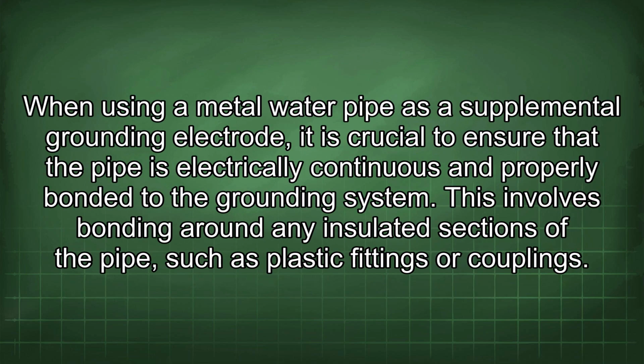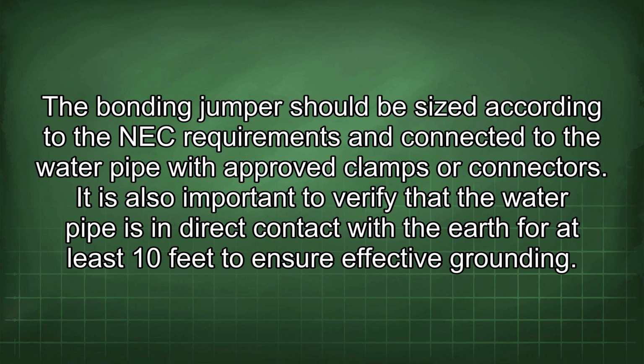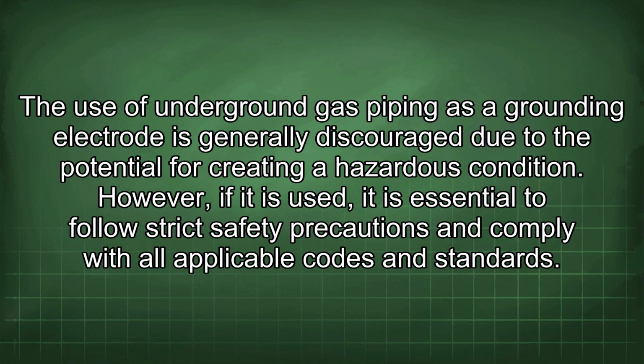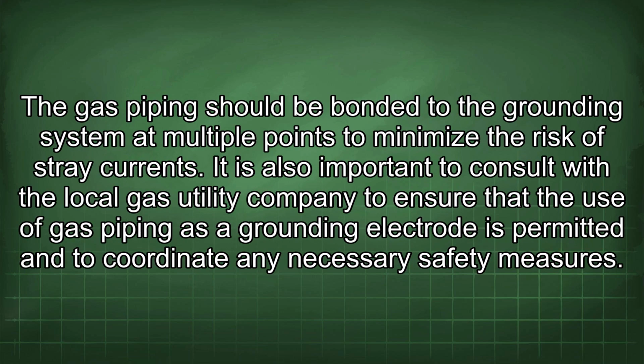When using a metal water pipe as a supplemental grounding electrode, it is crucial to ensure that the pipe is electrically continuous and properly bonded to the grounding system. This involves bonding around any insulated sections of the pipe, such as plastic fittings or couplings. The bonding jumper should be sized according to the NEC requirements and connected to the water pipe with approved clamps or connectors. It is also important to verify that the water pipe is in direct contact with the earth for at least 10 feet to ensure effective grounding. The use of underground gas piping as a grounding electrode is generally discouraged due to the potential for creating a hazardous condition. However, if it is used, it is essential to follow strict safety precautions and comply with all applicable codes and standards. The gas piping should be bonded to the grounding system at multiple points to minimize the risk of stray currents.